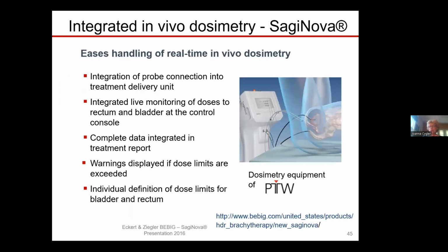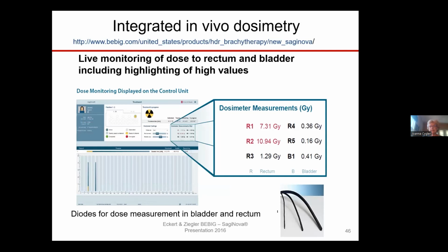This brings me to the end of the discussion of standalone in vivo systems. And now I would like to tell you about two integrated systems. So for brachytherapy, we have a commercial system integrated with the treatment unit. This HDR unit is called Saginova and has a diode-based in vivo dosimetry system that is integrated with the afterloader. The system provides instantaneous readout of those measurements and indicates the errors in the report, like here in red. So one can do the corrective action during the treatment or immediately after, before the next fraction. So one can only hope that all vendors would follow the lead of this company and integrate some in vivo dosimetry system with their afterloaders.